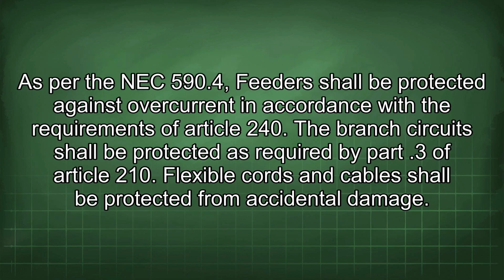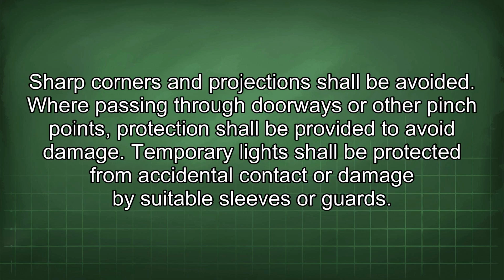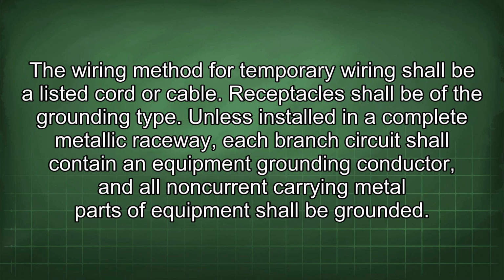As per NEC 590.4, feeders shall be protected against overcurrent in accordance with the requirements of Article 240. The branch circuit shall be protected as required by Part 3 of Article 210. Flexible cords and cables shall be protected from accidental damage. Sharp corners and projections shall be avoided. Where passing through doorways or other pinch points, protection shall be provided to avoid damage. Temporary lights shall be protected from accidental contact or damage by suitable sleeves or guards. The wiring method for temporary wiring shall be a listed cord or cable.